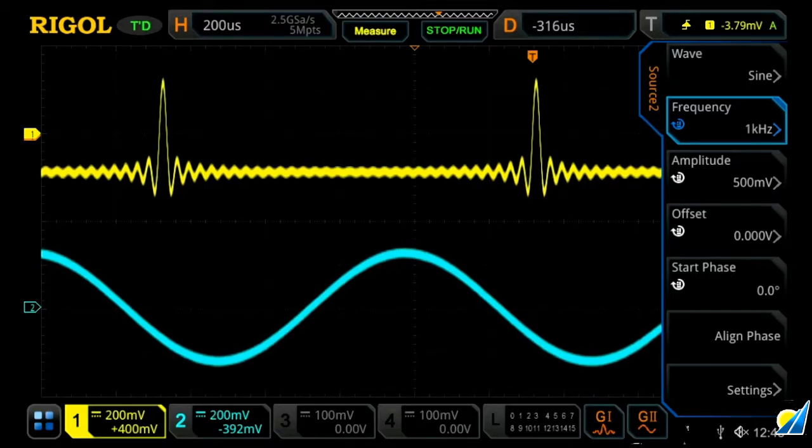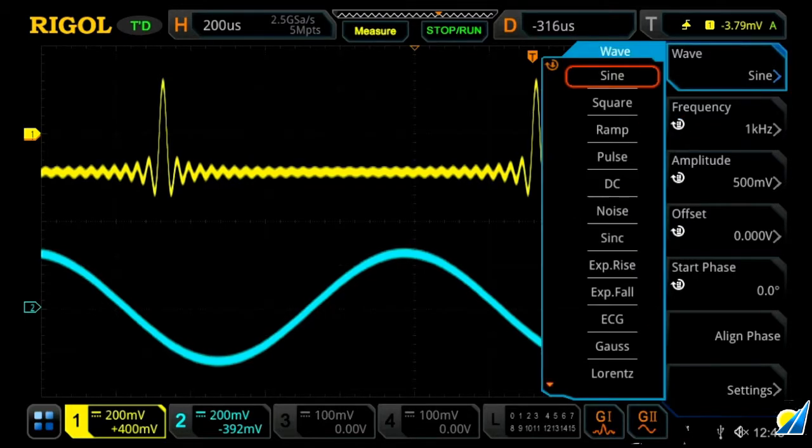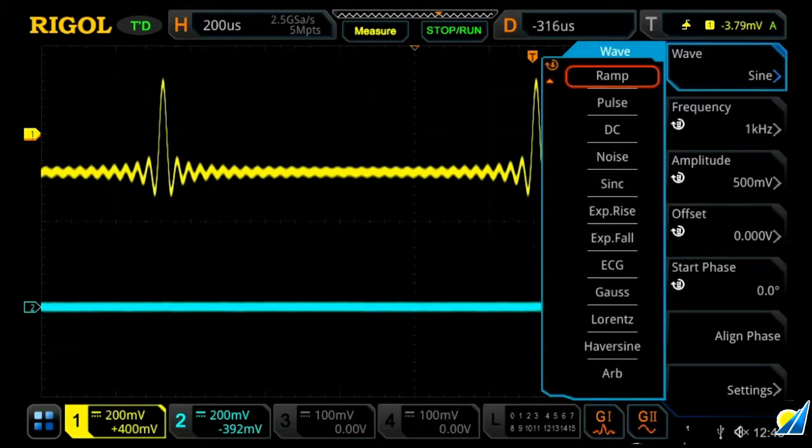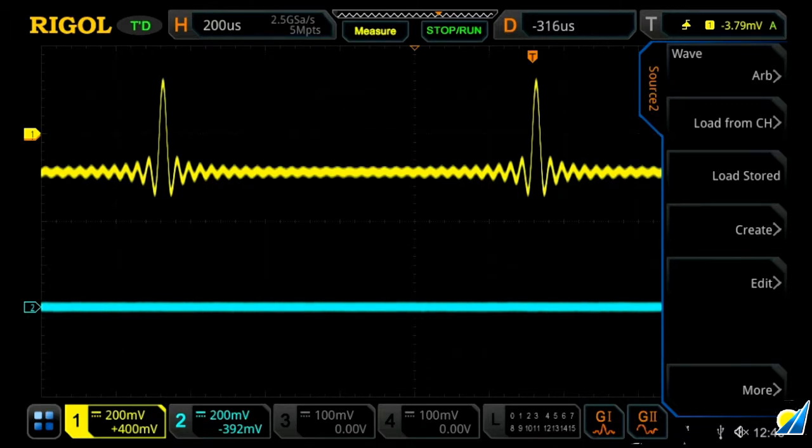And what we're going to do here is select our waveform. We're going to actually go all the way down and select arbitrary. And then from here this is where you can load a stored channel if you have a flash drive, you can create a function or edit one, or you can load one from a channel.